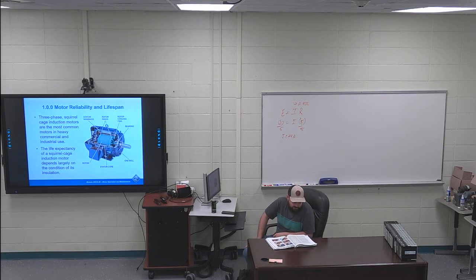Immediate next bullet point, single phasing, first sentence. You'll have a couple of questions come out of that first sentence. The loss of a single phase of a polyphase power source for a running motor can cause the failure of the remaining phase windings, because all the current flows through them over the motor if the motor is not protected by proper equipment, i.e. an overload protection. Everybody should know what single phasing is at this point. If you've done the motor control trainer, you lose a leg of power, you're going to be single phasing, and you should know what that noise sounds like in motors.